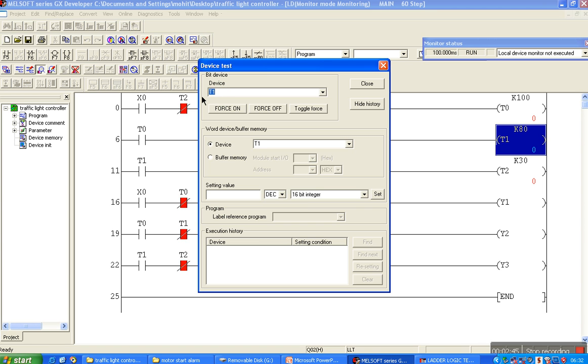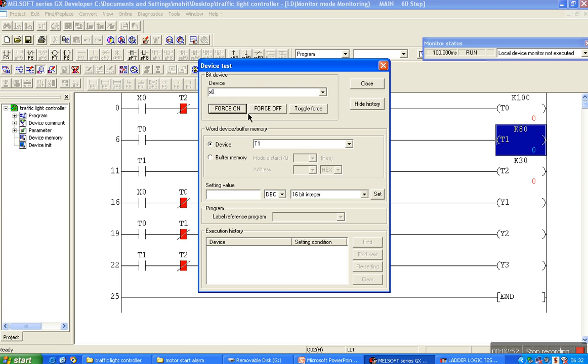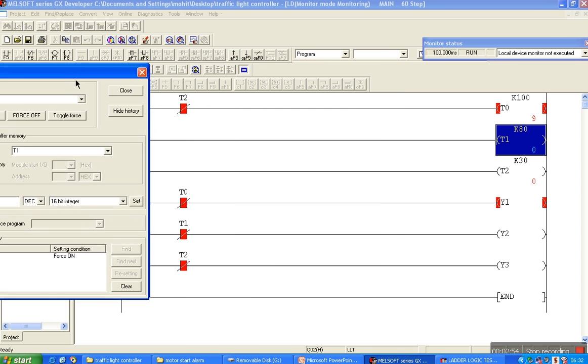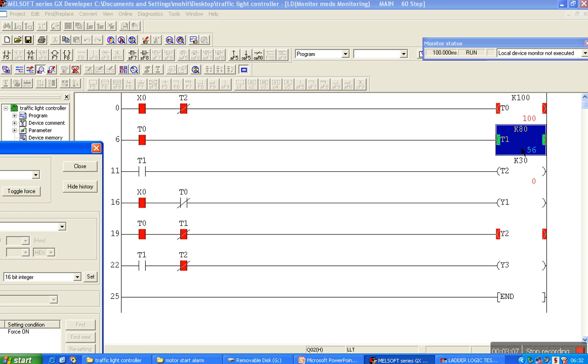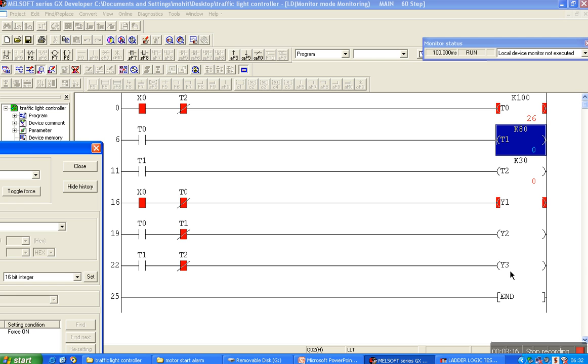Force on, the process is started. Timer T0 and Y1 run for 10 seconds, then Y1 turns off and the green light turns on for 8 seconds. After 8 seconds, timer T2 starts and Y3 is on. After 3 seconds the process repeats.